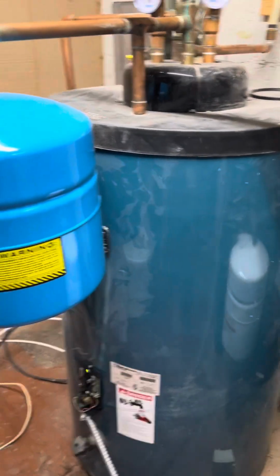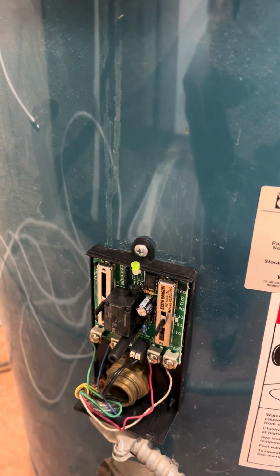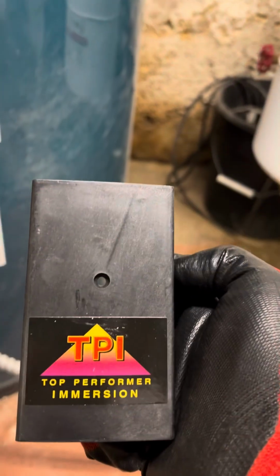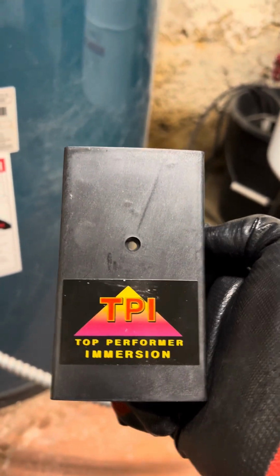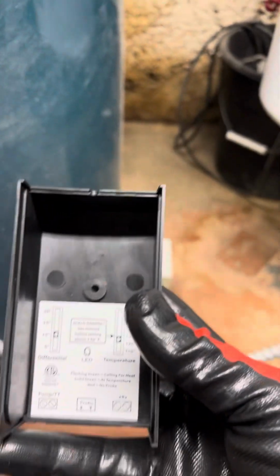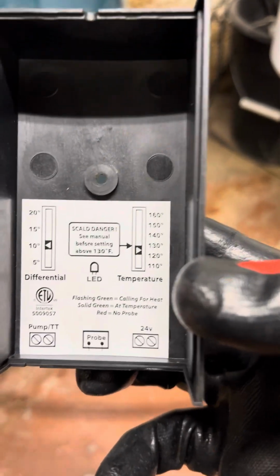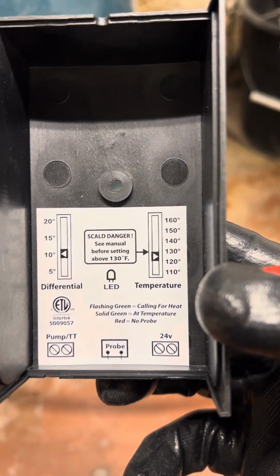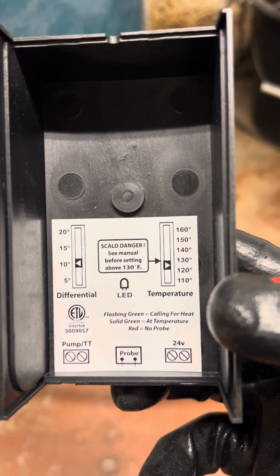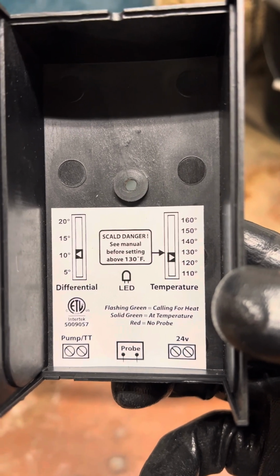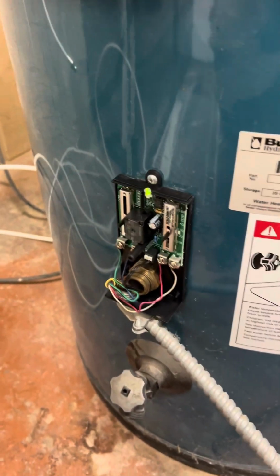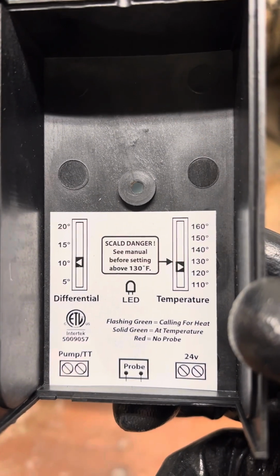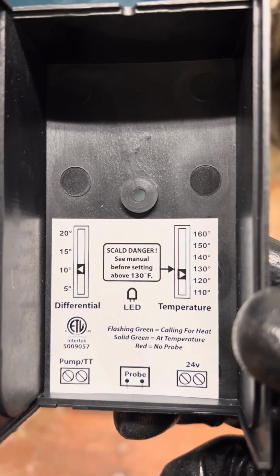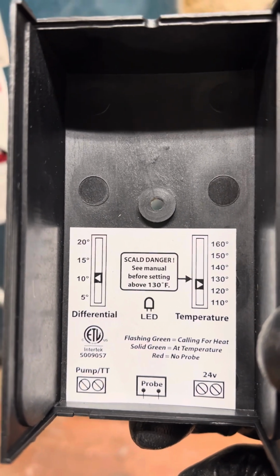Now, this is up and running because, see that? Now we got a blinking light. Before we didn't. All right, let me see on the back here. This is the front. Right? Top performer, immersion. Down here it says, I'm not sure if you can read it. All right. It tells you about the temperature, it tells you the differential. Flashing green, calling for heat, which it is. See? There you go. And then solid green, when it gets the temperature, so around 125, it's going to be solid green. And then red, no probe.